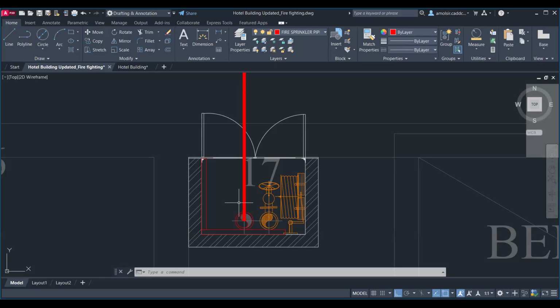See, the hose cabinet gets water from a wet riser, or you have a system with an underground water tank. The fire pump mainly operates, and the main and jockey pump accordingly will be operating. Then the riser pump will be receiving the water in the vertical pipe shaft accordingly, and then the water will be discharged for firefighting. So water is not directly connected locally, it comes from a central firefighting system, and the hose cabinet is just the usage point. Mostly inside the hose cabinet, we are having a hose pipe or nozzles connected over here. Fire hose cabinets are connected to wet riser systems, which is supplied by fire water tanks through the pumps. I hope that is clear.